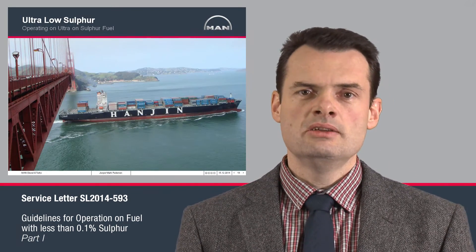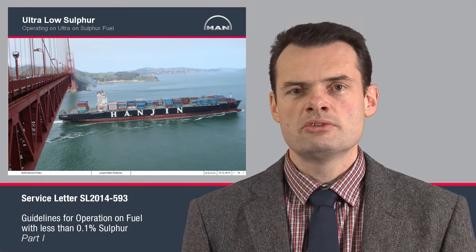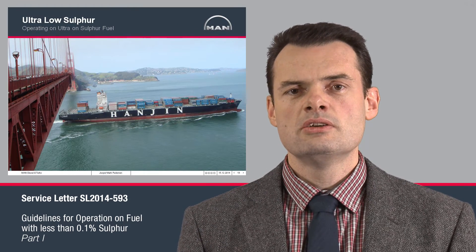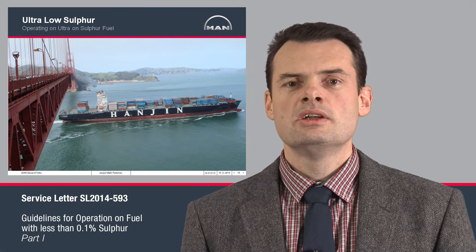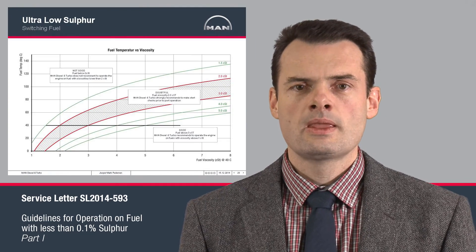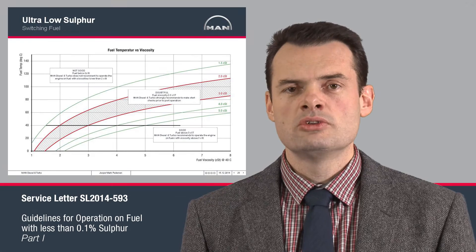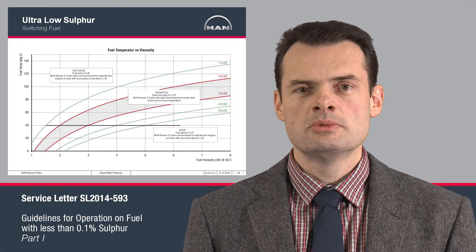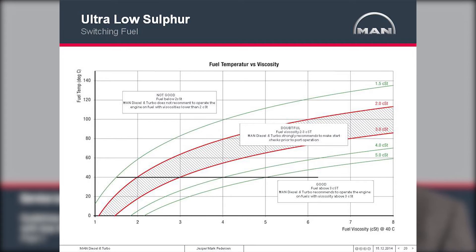We have gained considerable experience from the 2009 switch in California, where the emission rules in the CARB area made it necessary for ships to operate on MGO. The key experience was that it is very important to keep an eye on temperatures in the fuel system itself. As the engine slows down for maneuvers, fuel oil is recirculated and heated by the pumps and the engine, causing viscosity to drop — making it crucial to cool the fuel to avoid seizures inside the fuel pumps.